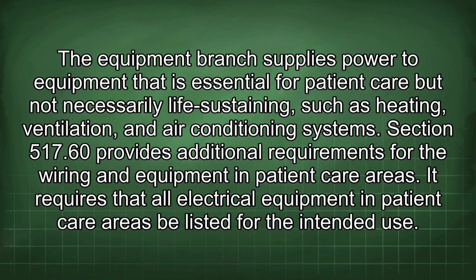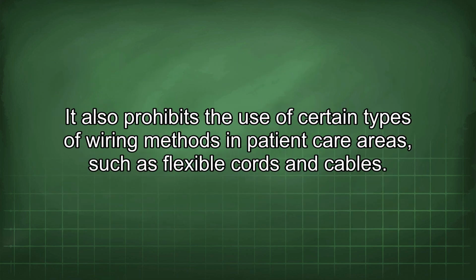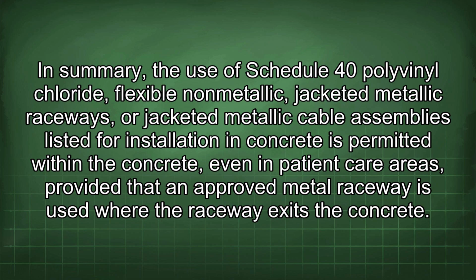Section 517.60 provides additional requirements for the wiring and equipment in patient care areas. It requires that all electrical equipment in patient care areas be listed for the intended use. It also prohibits the use of certain types of wiring methods in patient care areas, such as flexible cords and cables.